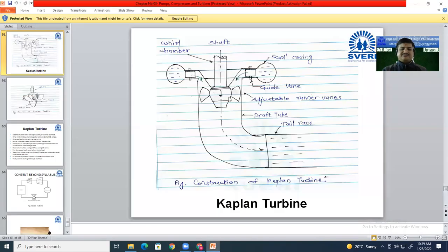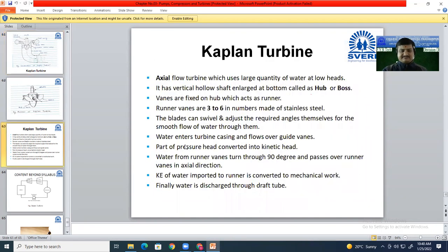So this is the mechanism, and I think now from this animation, the things are clear to you how such turbines are working. Water from the casing is coming through guide vanes and it is entering the whirl chamber. And at the whirl chamber, whirls are generated. Water strikes the runner blades. Runner blades are adjustable and runners start rotating. When runner blades are moving, the hub is started. The hub will start its rotation and the shaft is connected to it, which is further connected to the generator.